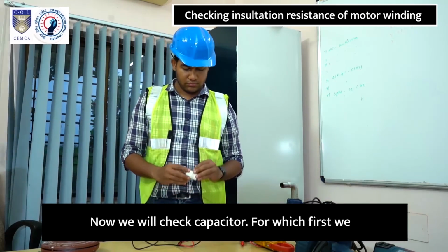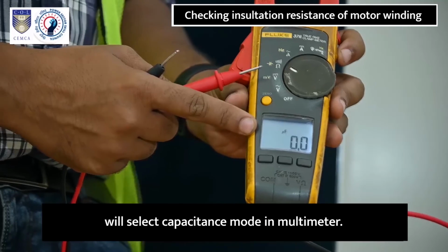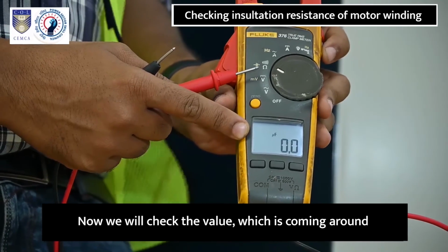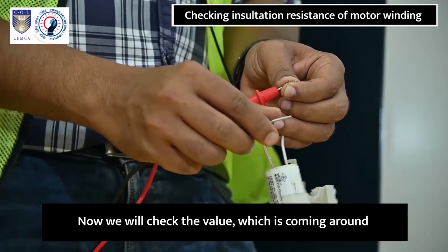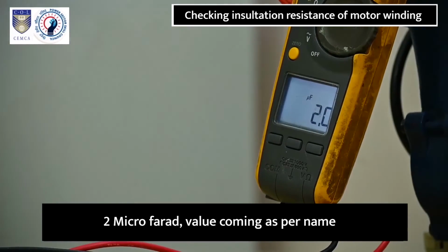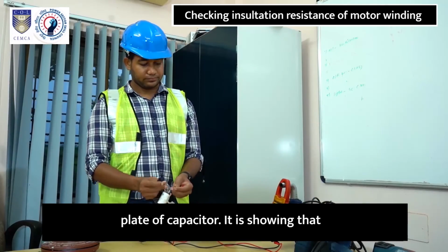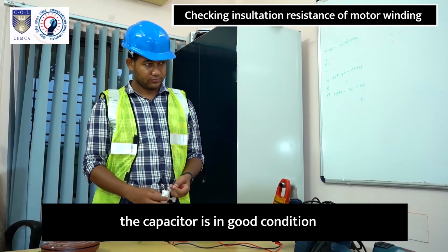Now we will check the capacitor, for which first we will select capacitance mode in the multimeter. Now we will check the value, which is coming around 2 microfarad. The value is coming as per the nameplate of the capacitor. It is showing that the capacitor is in good condition.